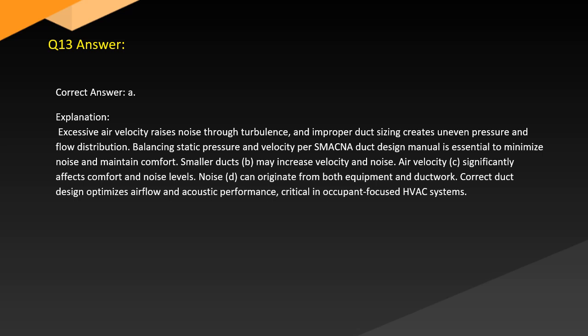Air velocity, C, significantly affects comfort and noise levels. Noise, D, can originate from both equipment and ductwork. Correct duct design optimizes airflow and acoustic performance, critical in occupant-focused HVAC systems.